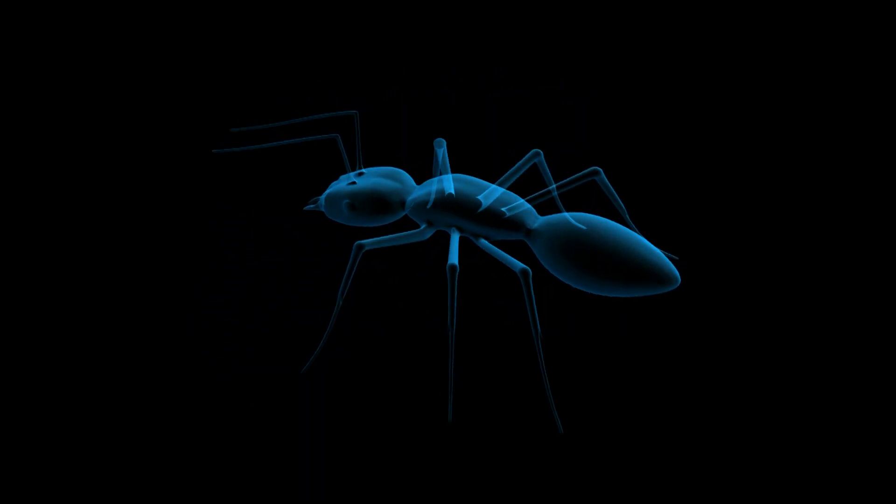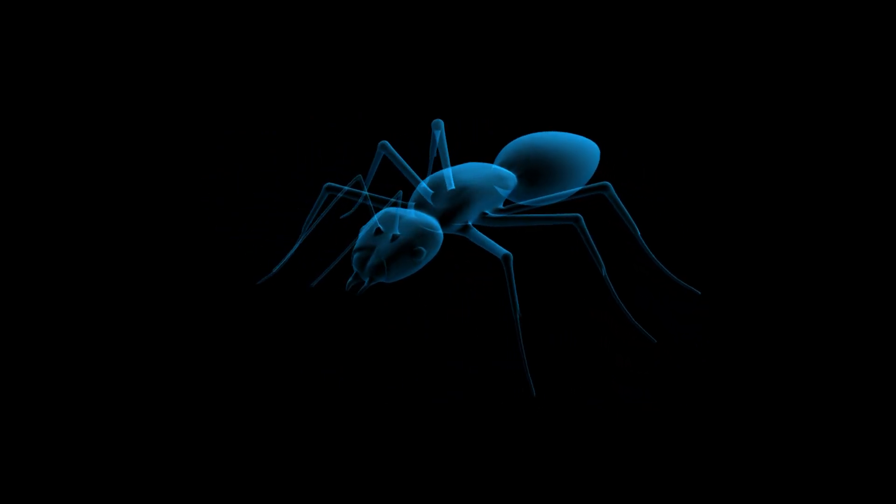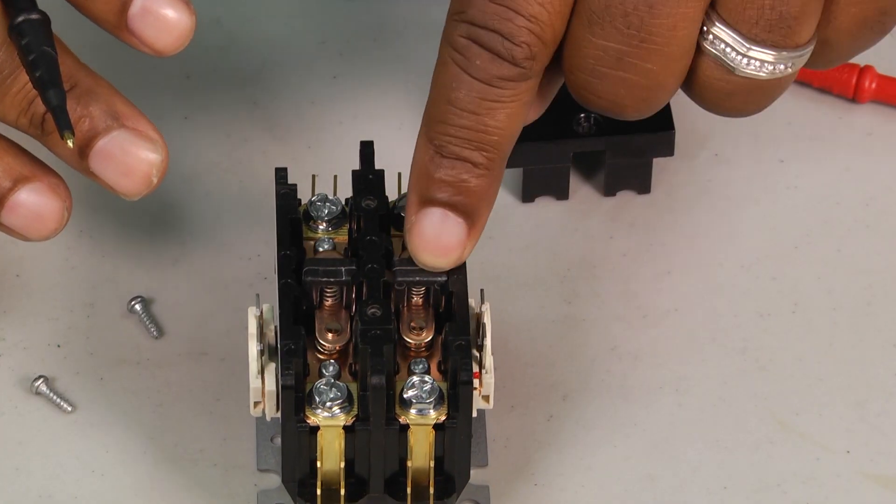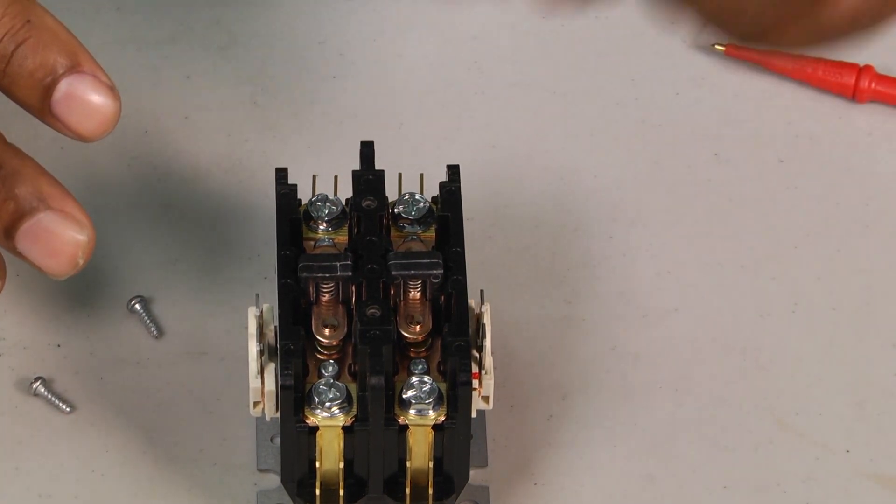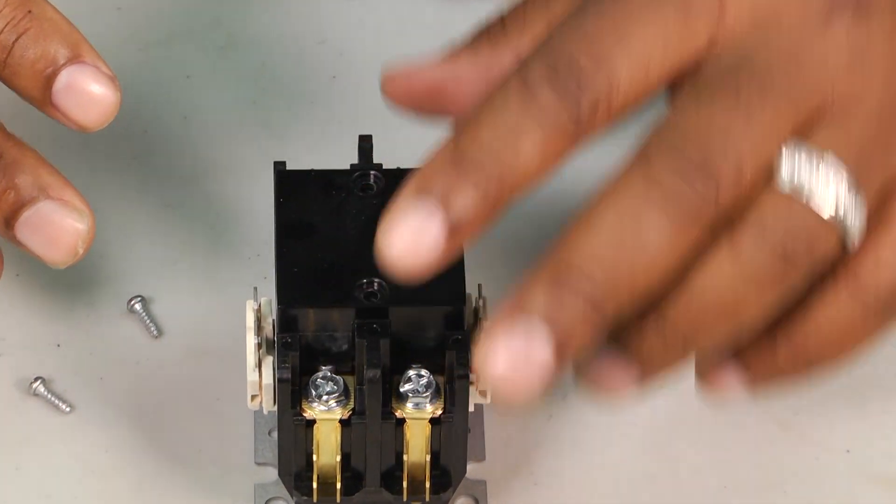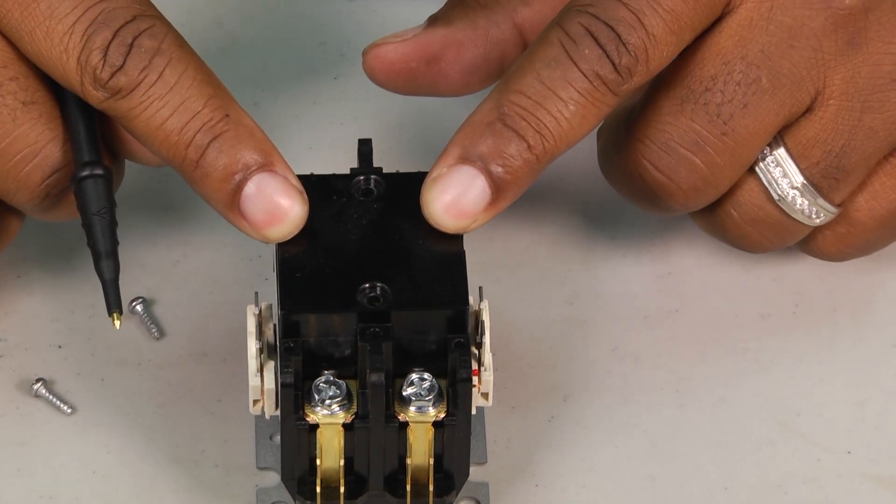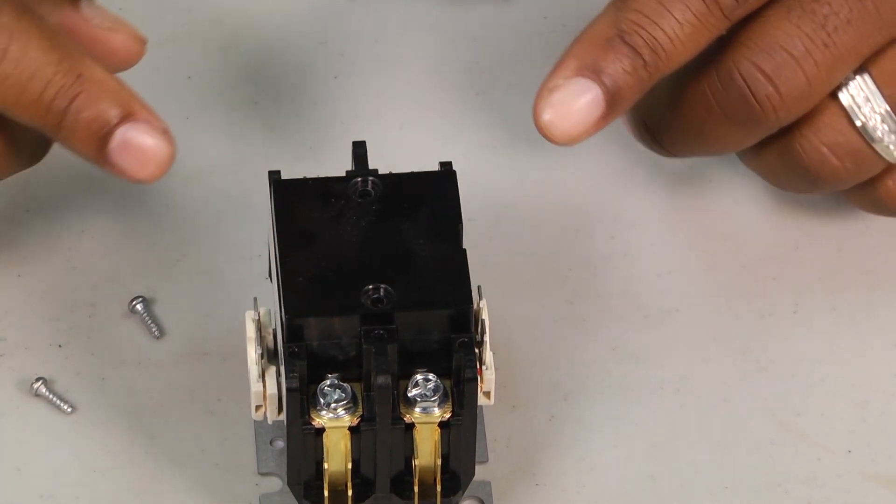They crawl in there, and then those ants build up, and the ants get in between the contacts, and the contacts cannot make contact. That's why it's a good thing to have this little protective device on there to keep ants from getting inside your contactor.